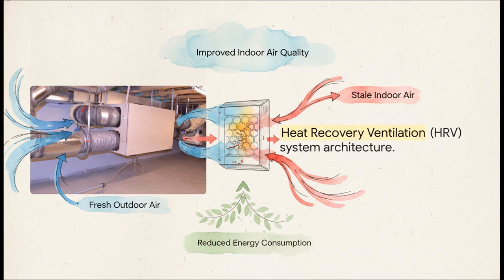But the real genius is the heat exchange core inside that casing. As the two air streams pass each other, without physically mixing, which is key, the system continuously preheats the incoming cold, fresh air using the warmth of the outgoing stale exhaust air. It drastically reduces energy consumption while keeping thermal comfort incredibly high.